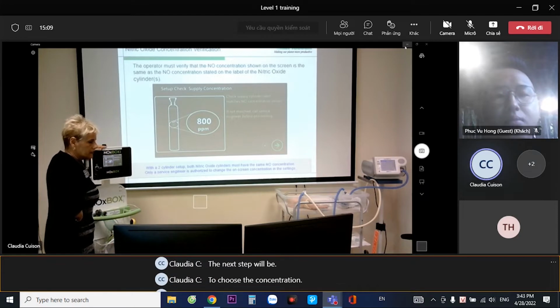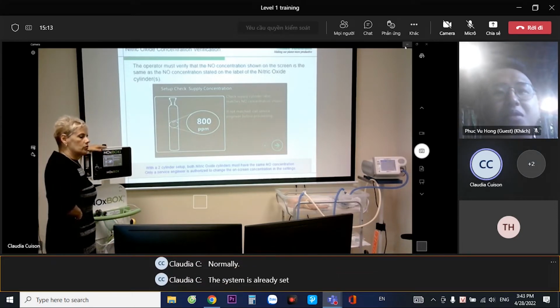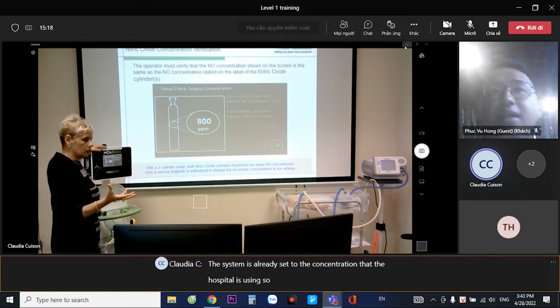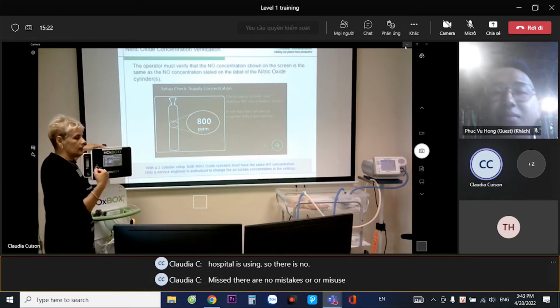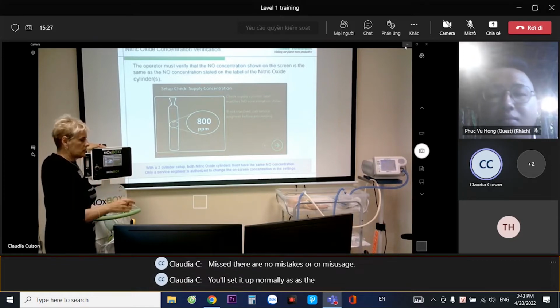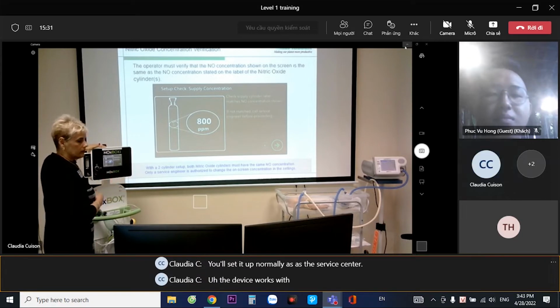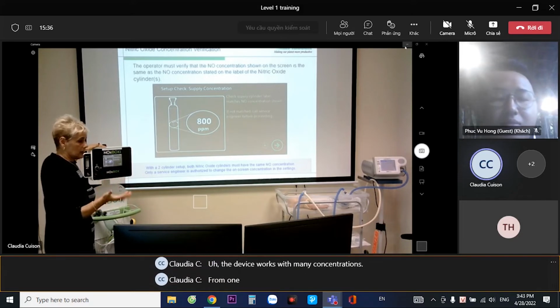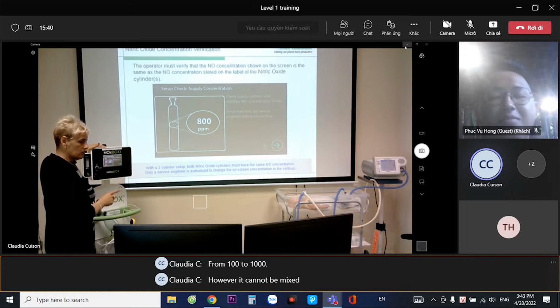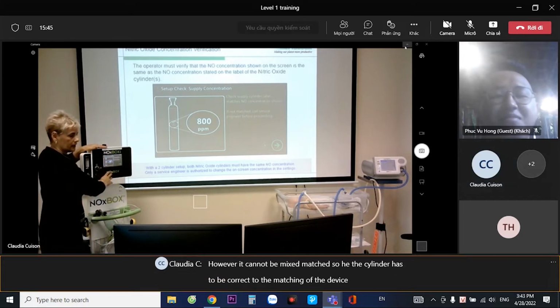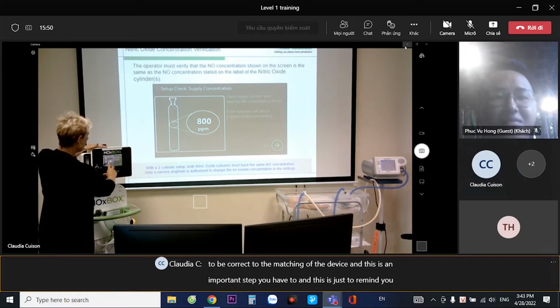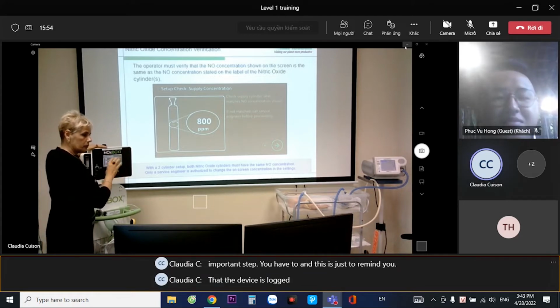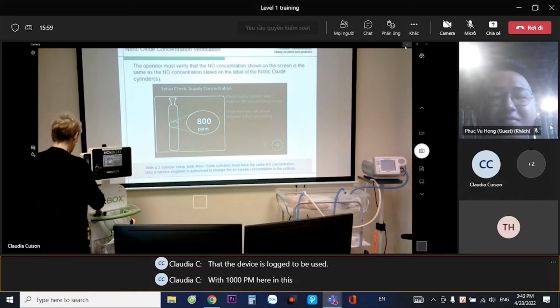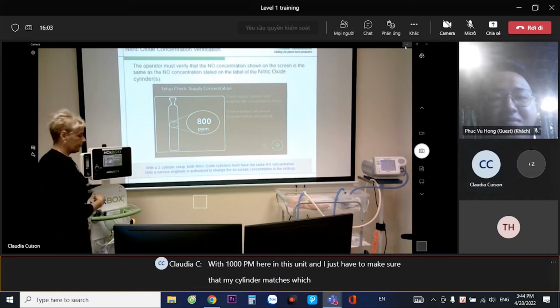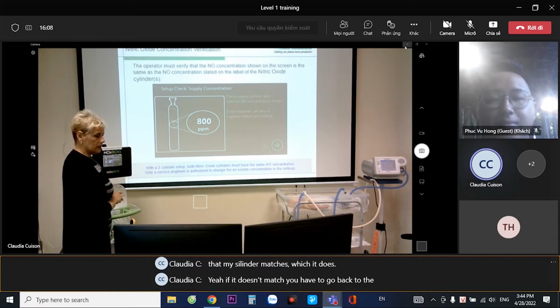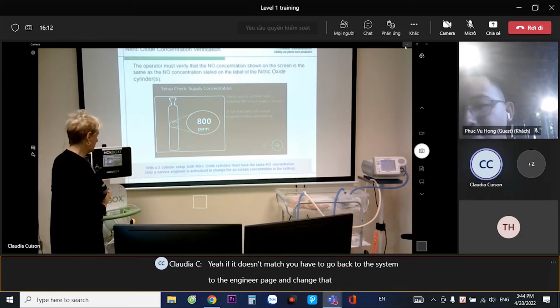to choose the concentration. Normally the system is already set to the concentration that the hospital is using, so there are no mistakes or misusage. You set it up normally as the service center. The device works with many concentrations from 100 to 1,000. However, it cannot be mix matched. So the cylinder has to match the device, and this is an important step. This is just to remind you that the device is locked to be used with 1,000 ppm in this unit. I just have to make sure that my cylinder matches, which it does. If it doesn't match, you have to go back to the system, to the engineer page, and change that correctly.